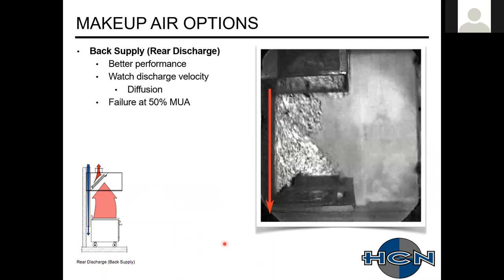Next option is the back return. This was actually pretty well received and did really well. It's one of the better systems that they tested. And the big thing with the back return or back wall is you could have a failure rate at, they were going with 50% of your exhaust rate. And the big thing with that is the discharge velocity coming out. Depending on how long this back return was, if you're doing this, you definitely wanted to do it below the cooking appliance. But you needed that distance between the pilots and that to be about, I think it was 24 to 18 inches, somewhere in there, because you want to keep that velocity down. If it's going too fast, you're going to blow out your pilots, you're going to have problems.